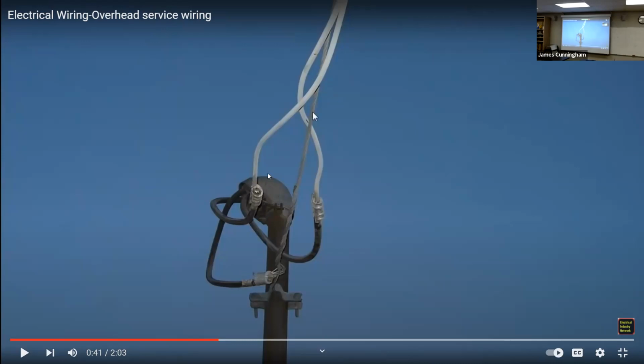So you have your two 120 lines, and then he's going to explain what the neutral wire is here. It serves two purposes. It's aluminum, but it has a steel cable inside of that called the carrier cable. Yeah, so the carrier cable inside the neutral also is used to support the wires so that they don't fall down. So you have a steel cable in the center of that that's attached to your pole here, and it will support the other two wires.